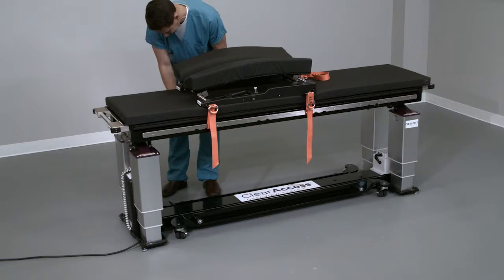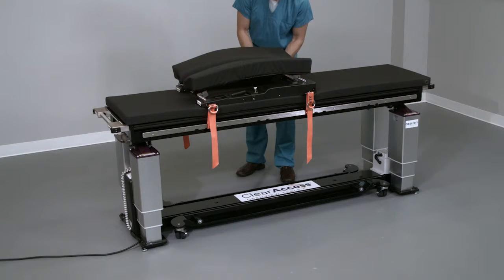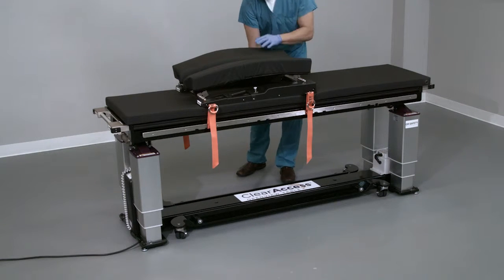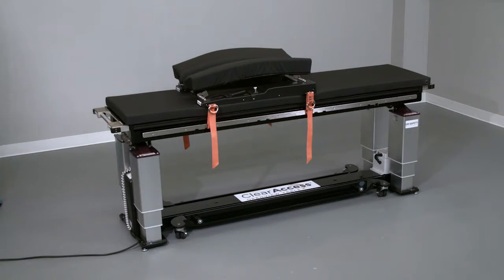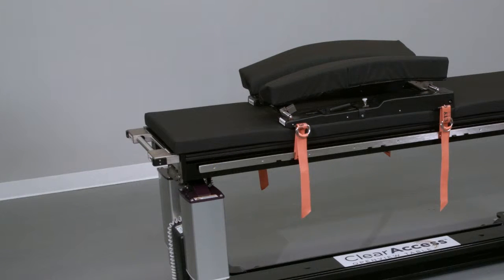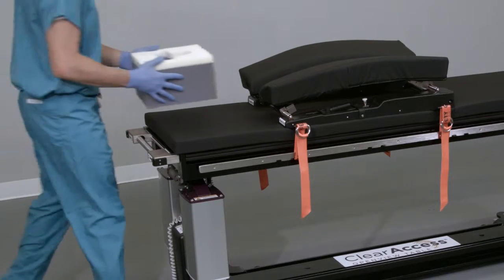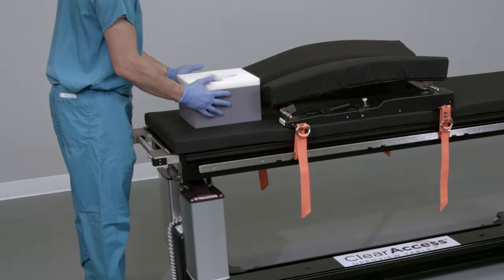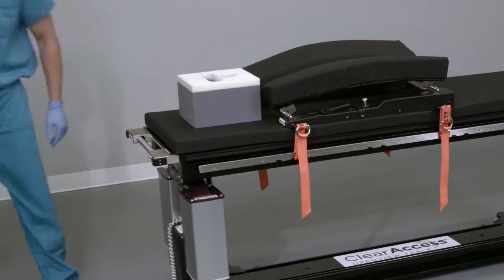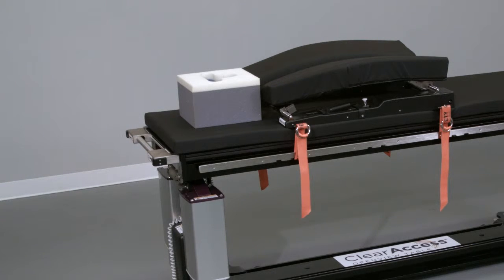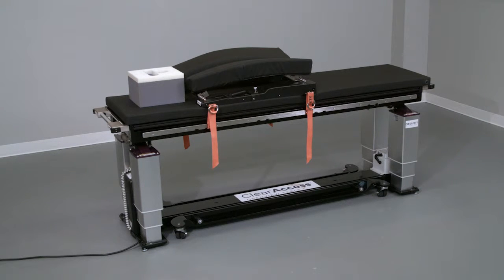Note that the safety straps are necessary to ensure that the FlexFrame will remain in place, especially in instances of extreme angulation, including lateral roll, Trendelenburg, or both. Place the face pillow at the head end of the table, close to the FlexFrame and in the expected location of the patient's head.